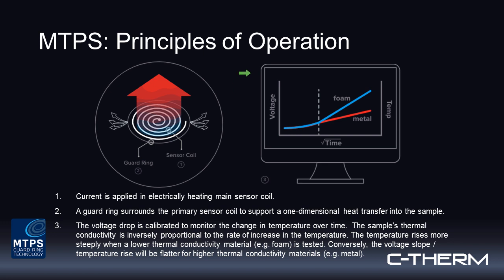You want to make sure that the measurement pulse stays within the boundary conditions of the samples for the duration of the measurement. So typically that requires a sample that's about 1 millimeter in thickness, and as the material would have a higher thermal conductivity, that minimum thickness would increase. So the higher the conductivity, the thicker the minimum thickness requirements.